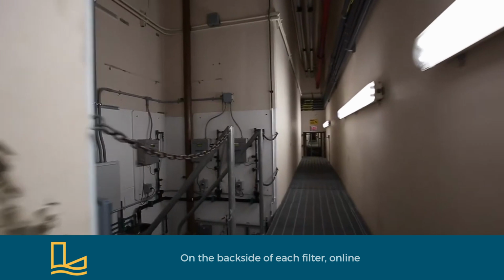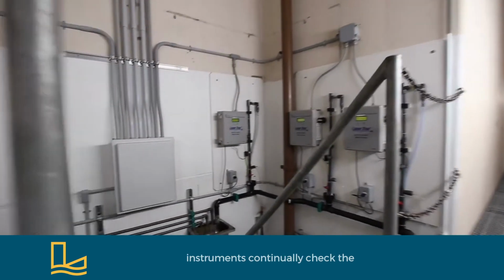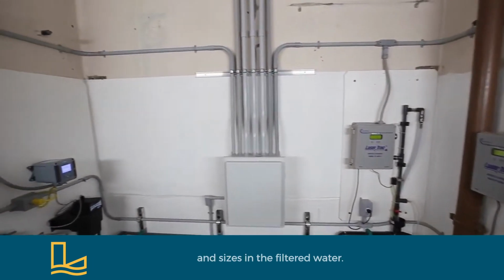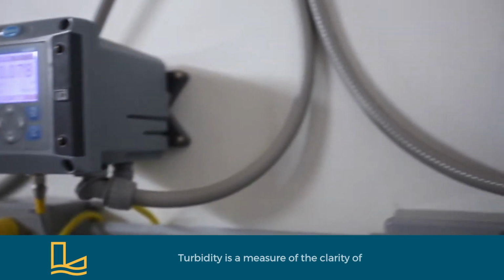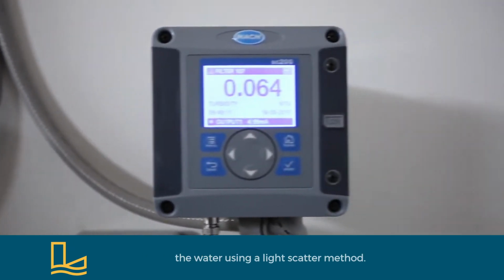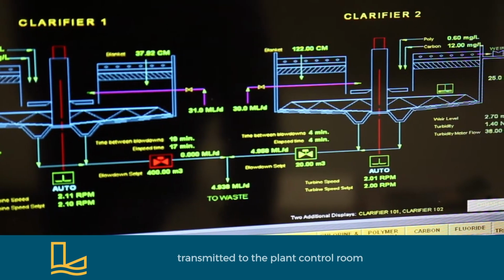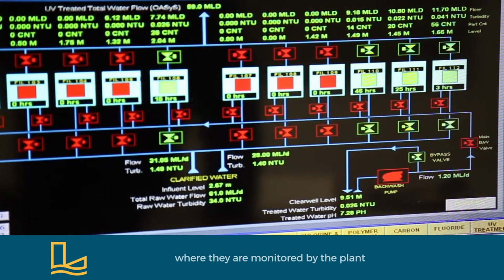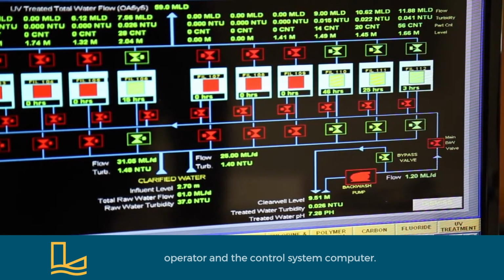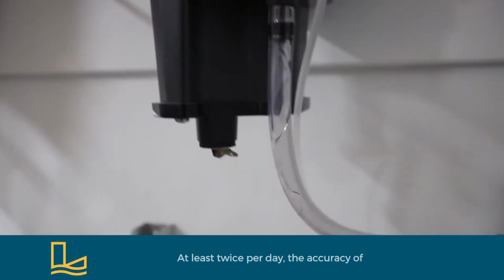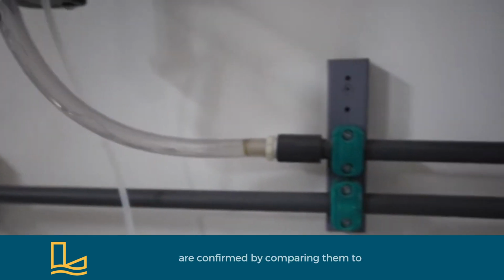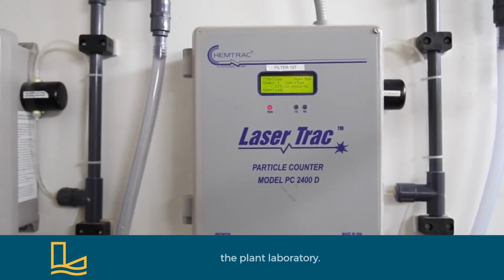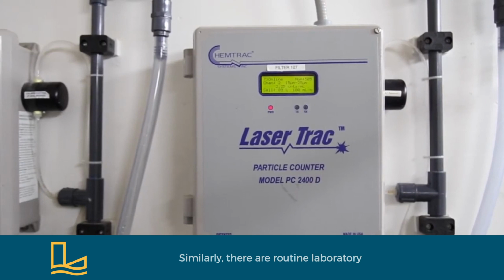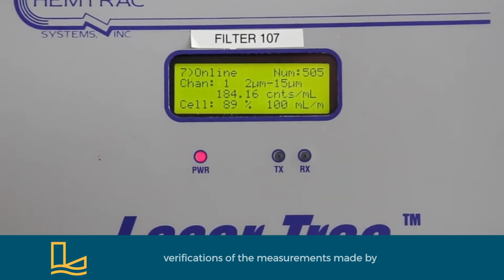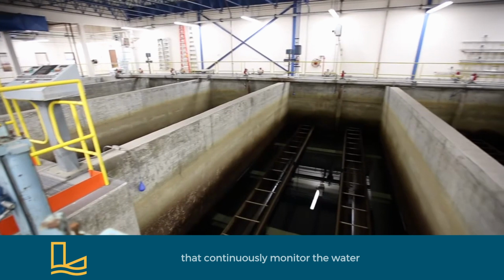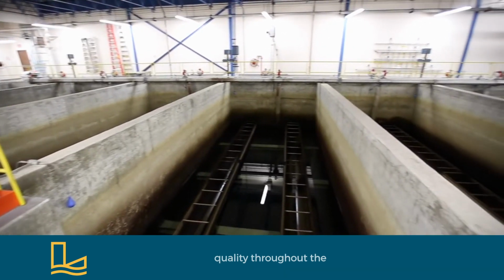On the backside of each filter, online instruments continually check the turbidity and particle counts and sizes in the filtered water. Turbidity is a measure of the clarity of the water using a light scatter method. These measurements are transmitted to the plant control room, where they are monitored by the plant operator and the control system computer. At least twice per day, the accuracy of these turbidity meters is confirmed by comparing them to measurements taken in the plant laboratory. Similarly, there are routine laboratory verifications of the measurements made by all of the online instruments that continuously monitor the water quality throughout the water treatment plant.